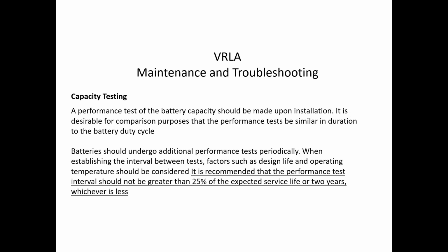Capacity testing. It's by far the best way to determine the health and what that battery is going to do for your load when called upon. The IEEE recommends performance testing on valve-regulated batteries because they're so unpredictable, and this actually goes back to their earliest generations of these batteries. That's for various reasons: quality control, the way plates were formed back then, the way the batteries were assembled. They were very unpredictable in the way they were going to act out in the field.